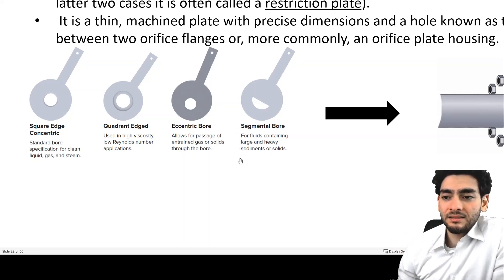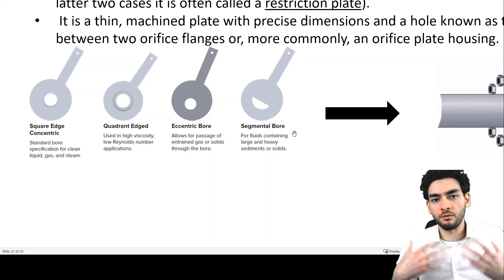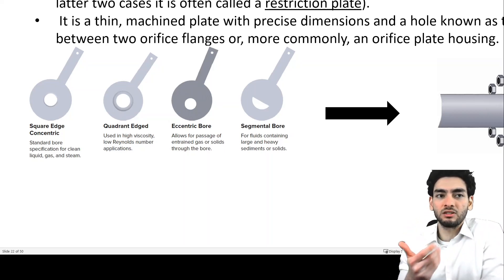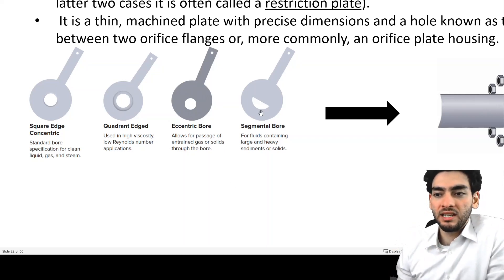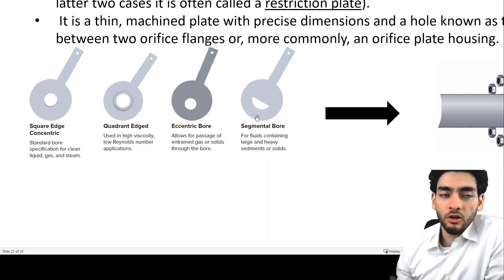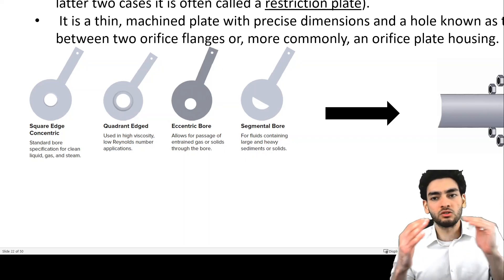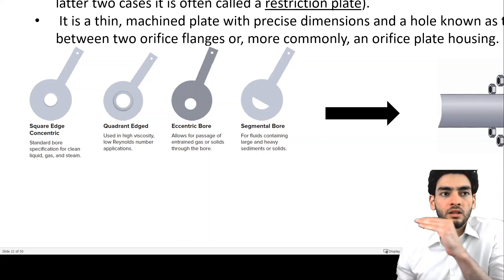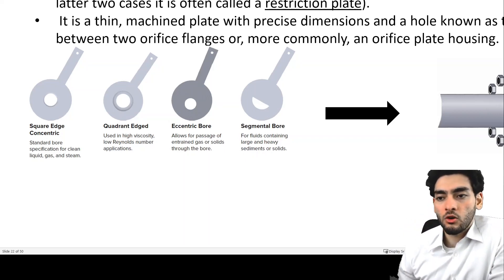...if you have a process that contains slurry with solids that might sediment, then you would need the opening of the hole to be closer to the bottom of the pipe such that there's no sedimentation or solids that accumulate under the opening.